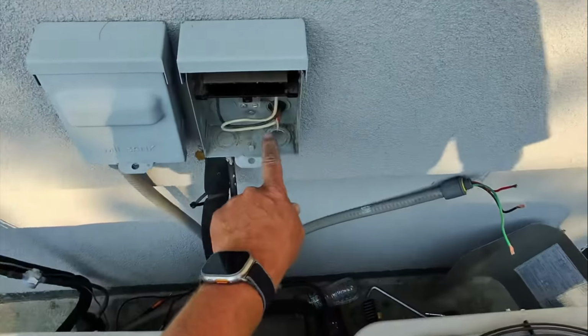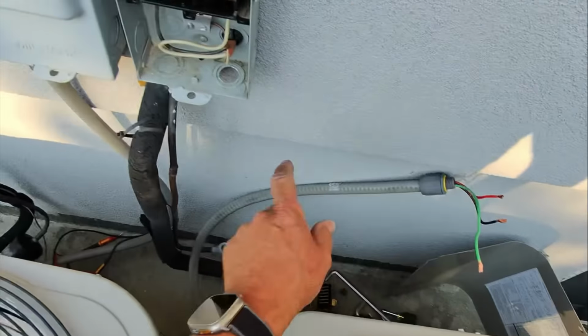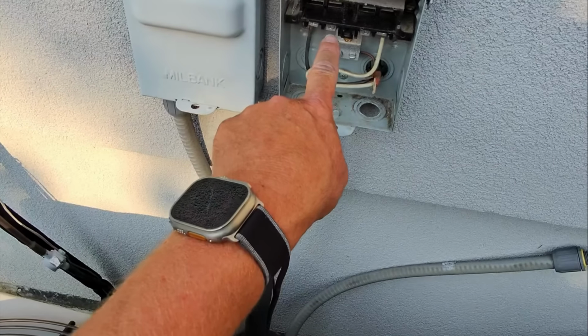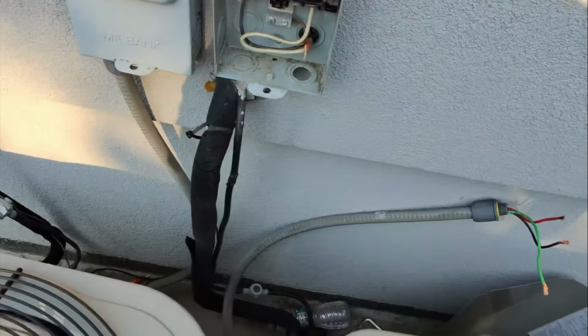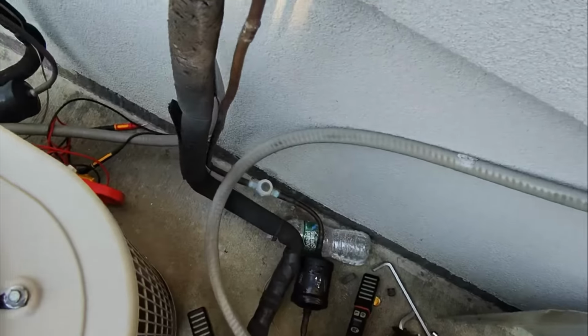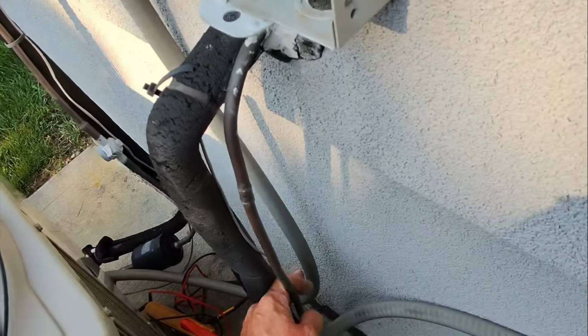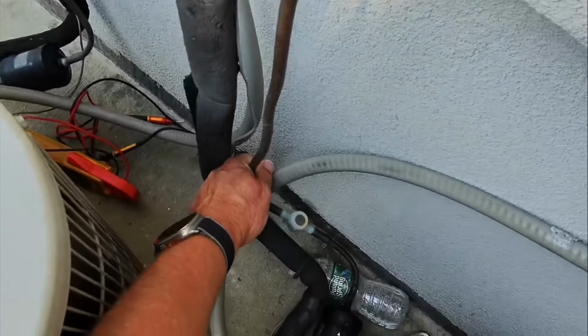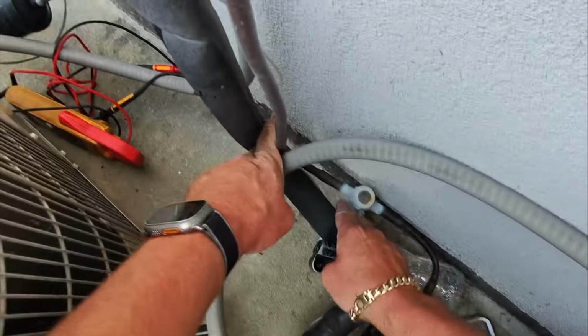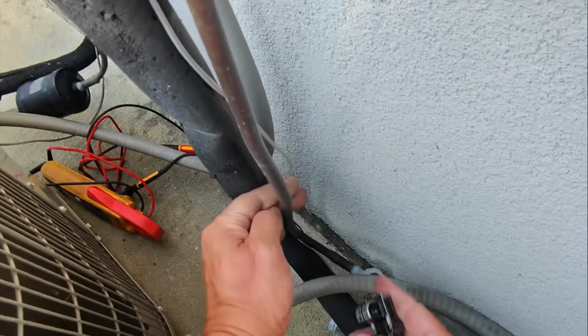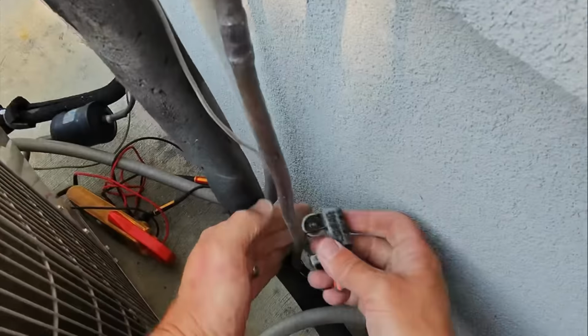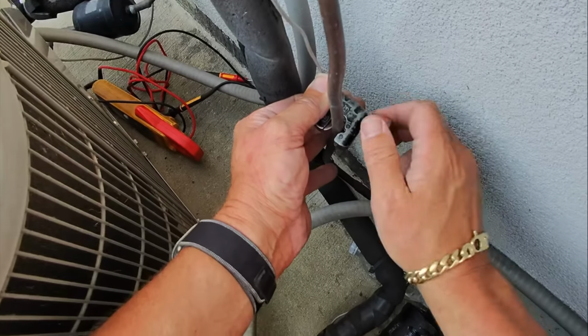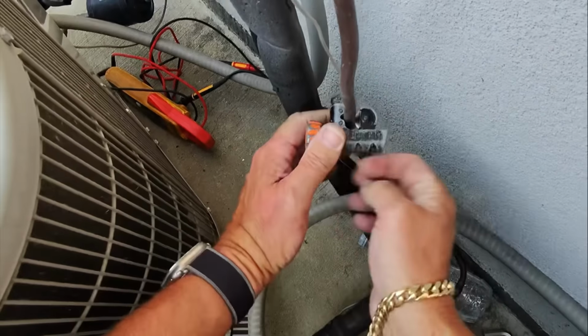I removed the whip, half-inch Liquid-Tight from the load side—L1, L2, and our ground. Now that the system is pumped down, we're going to cut this line set. Let's cut that right here. I'm going to have to extend this anyway, so...